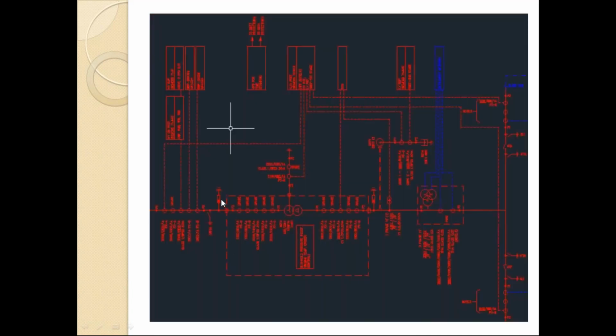For example, this is a transformer for some other project, where they have used a two-winding transformer. This is the neutral part. If you see the protection, this area is the overall transformer protection. On the HV side and the LV side they have used mesh corner, and on the LV side REF. Everything is combined, and this is the overall protection. These are the main differences between the auto transformer and the two-winding transformer.